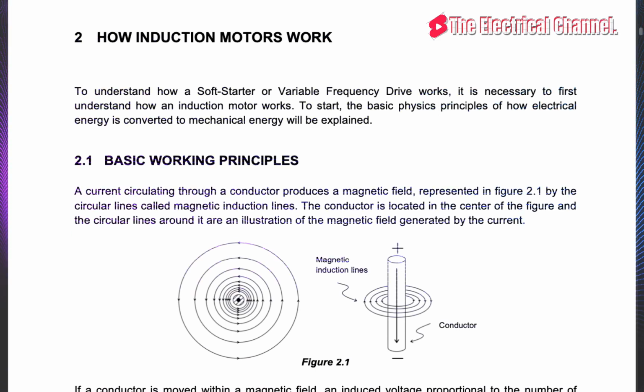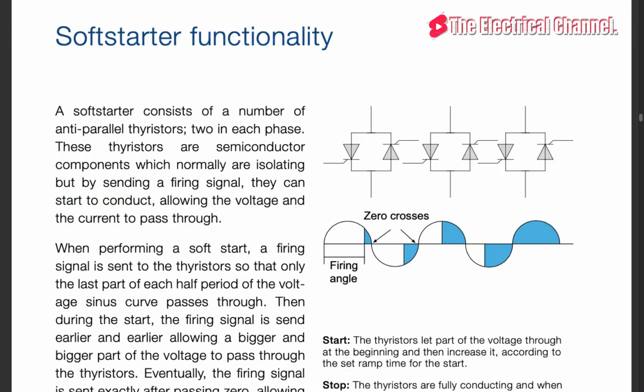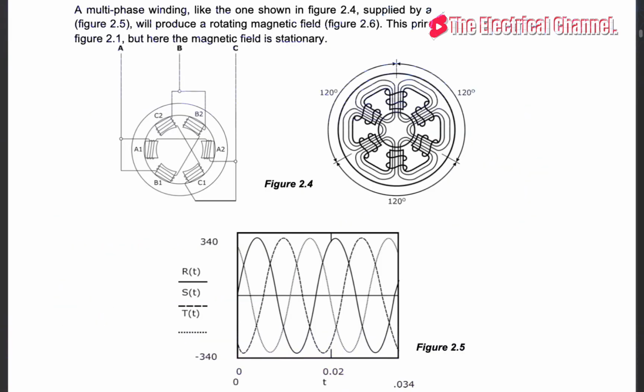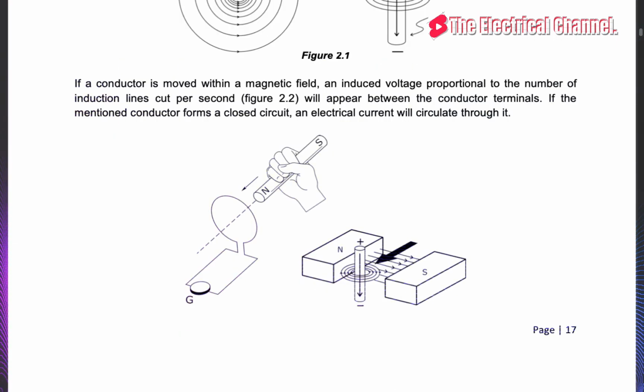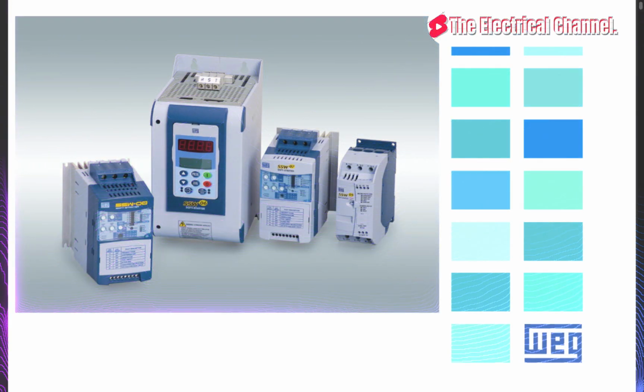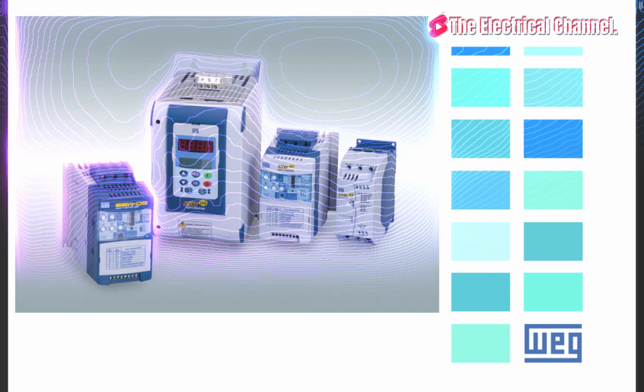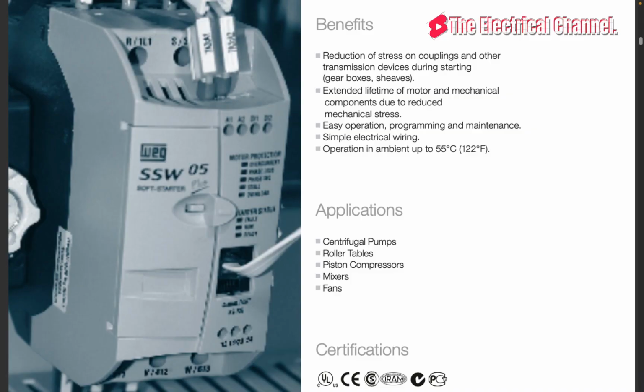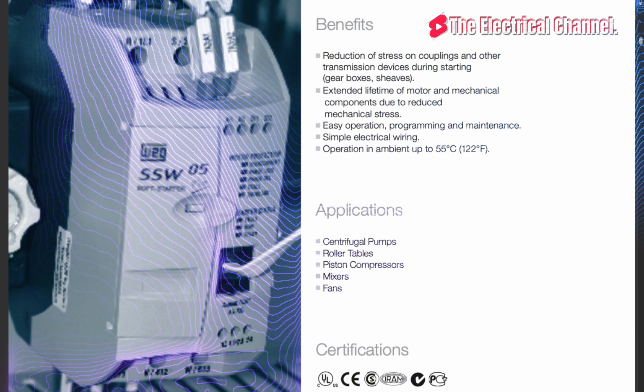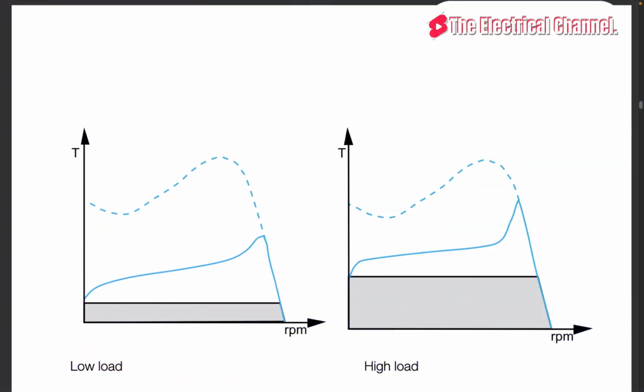Some soft starters, like the PSD-B range, have the possibility to use different parameter sets for the different motors. This is needed to achieve a good start if the motor sizes are different or if the applications are different. Most soft starters cannot soft stop more than the latest started motor. Usually, separate protections need to be used for each of the motors.